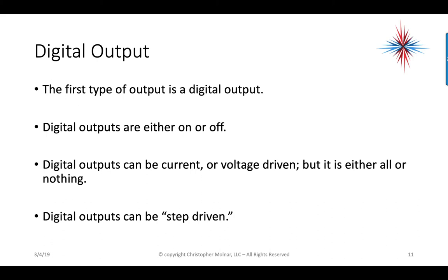The first type of output is the digital output — it's either on or off, all or nothing. For example, if we're using a 24-volt output device, it is either receiving 24 volts or receiving nothing. Digital outputs can also be step-driven. There's a device called a step motor: we send a digital signal, a blip of 5 volts, and the valve opens to the next position. If it's not open far enough, we send another 5-volt signal, and the valve opens to another position.